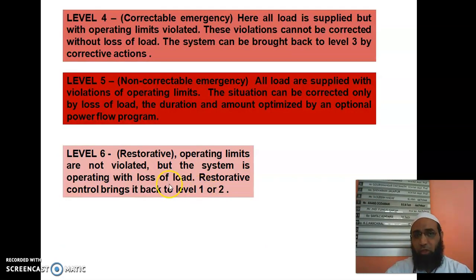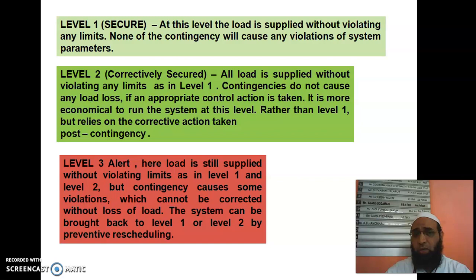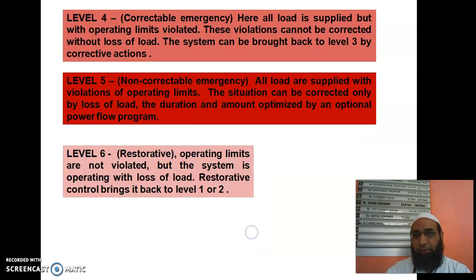Level 3 is the alert level. Load is still supplied without violating limits, as in levels 1 and 2. However, contingencies cause some violations which cannot be corrected without loss of load. The system can be brought back to level 1 or level 2 by preventive rescheduling.